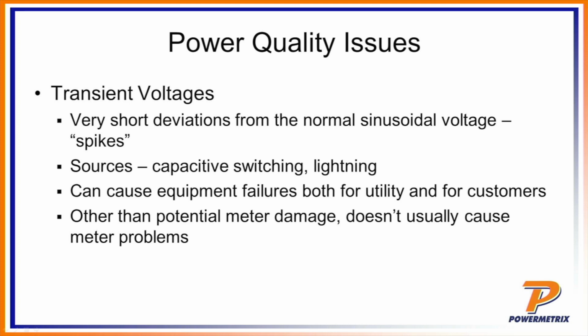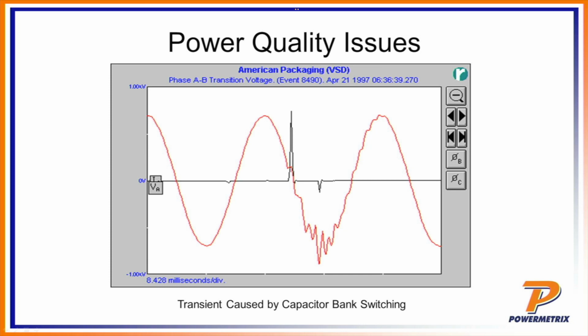So if you have cap banks that are being switched in and out of the system, sometimes you'll get a large spike when you do that. Here we have another visual example showing once again the voltage and the current of a system. And so what we see is that the voltage is going along nice and clean until you get this huge spike in current, and then you see a large distortion in the voltage waveform. But you'll note that basically the voltage has recovered not even one cycle into the future. And so once again, that shows there's a lot of resiliency in the distribution system to recover from these sorts of events.